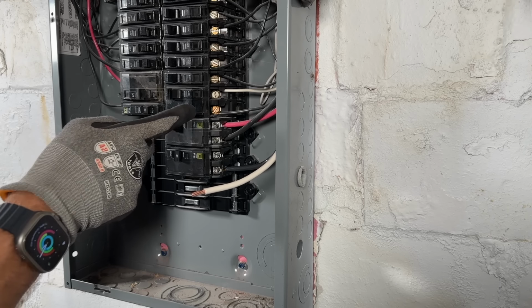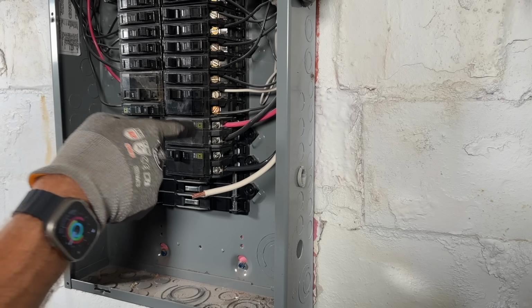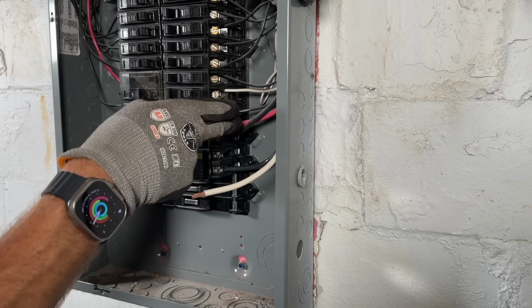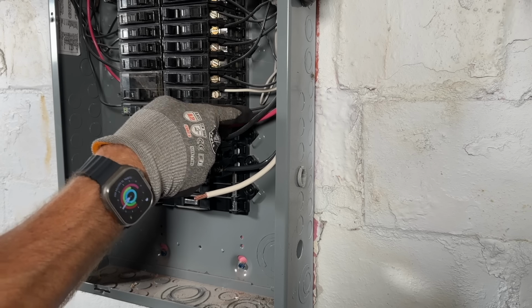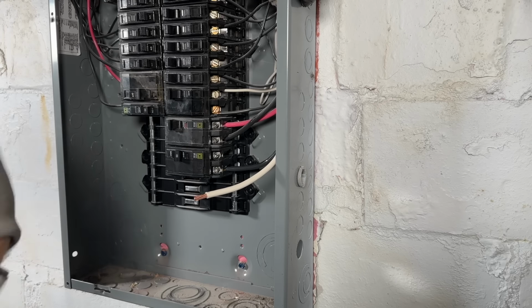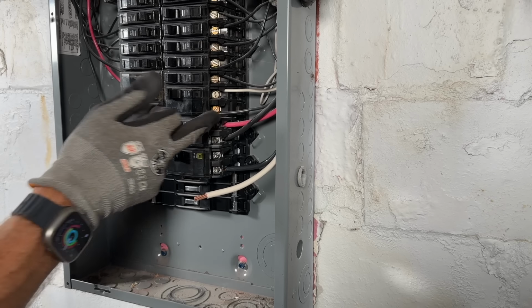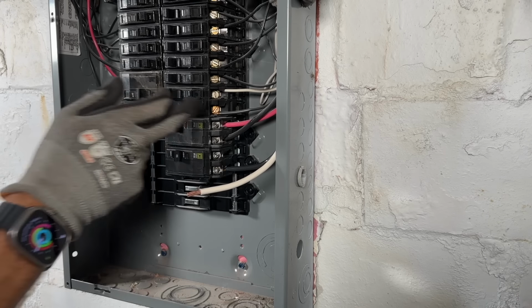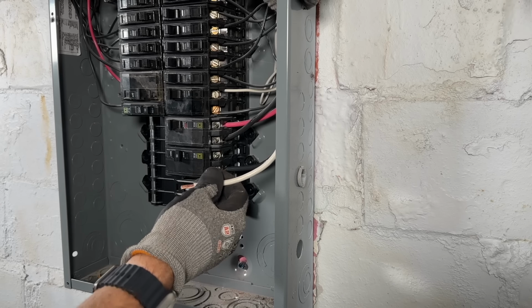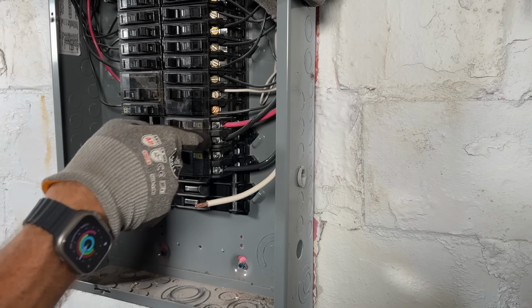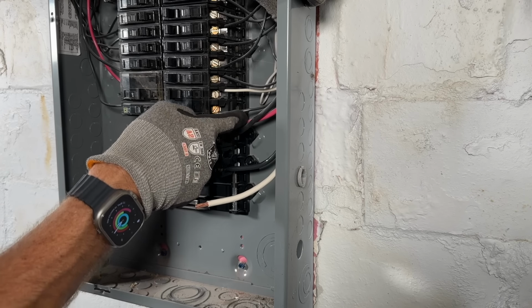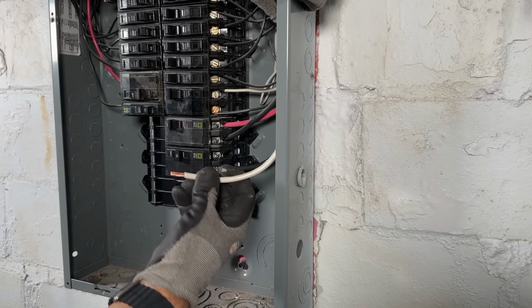For instance, if you had a 50 amp oven outlet that's 4-prong, where it has the two 120 phases, the two hot conductors, it has a neutral and it has a ground. So in this case, our white is equivalent to the red here for our second 120 phase, and that is what gives us 240 volts across the two different phases.